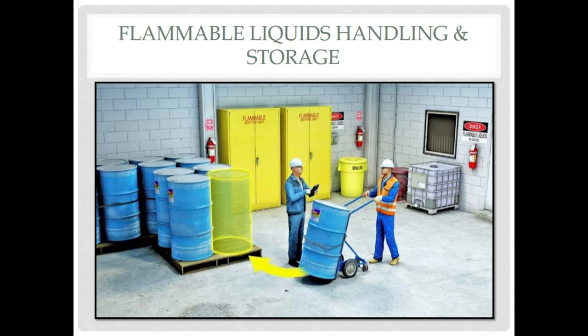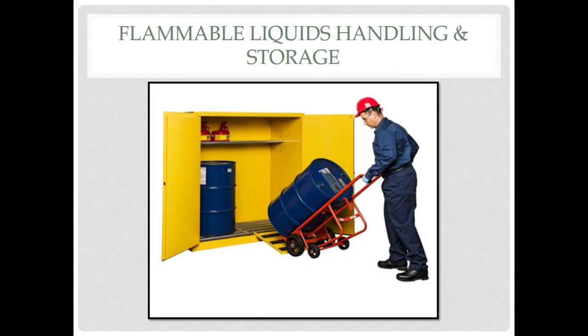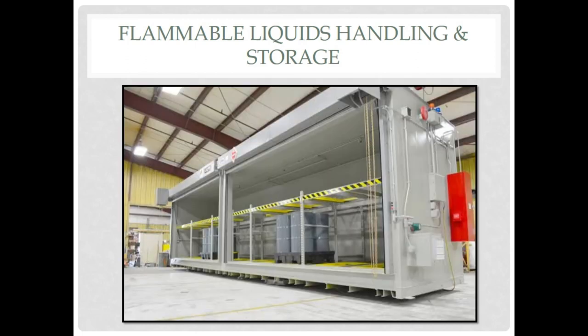The ideal storage scenario includes fire extinguishing media, spill kits, highly flammable cabinets, and proper separation of category 1 and 2 chemicals. Pallets and secondary containment should be in place. Personnel must wear proper safety shoes and use rubber-insulated equipment to prevent static charge buildup. Highly flammable drums should be placed in flammable cabinets. Real-time examples show smoke detection systems, foam suppression systems, and secondary containment in practice.